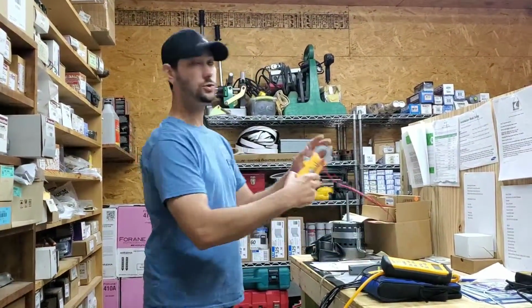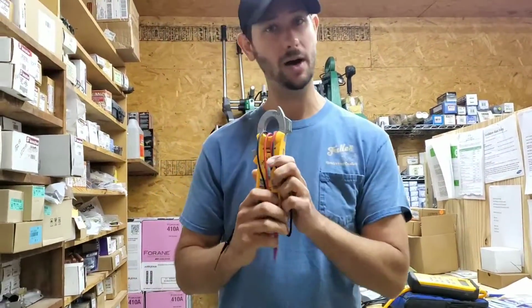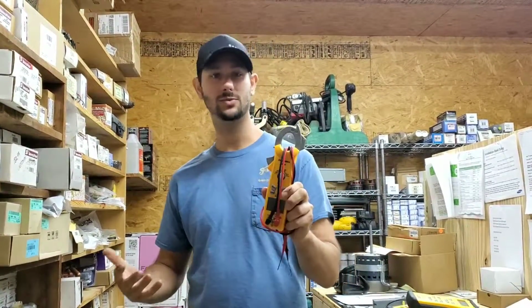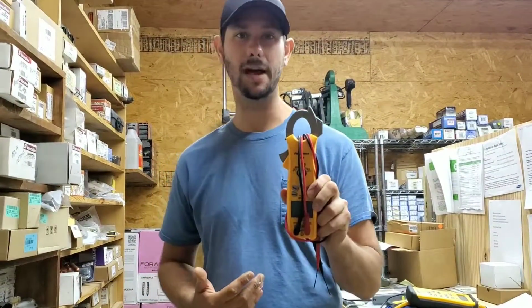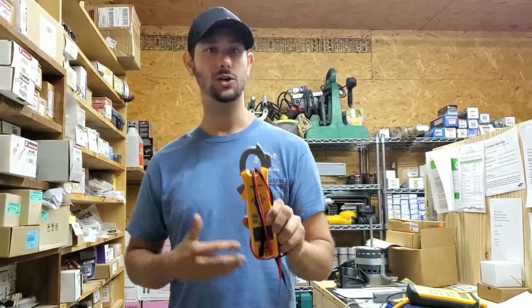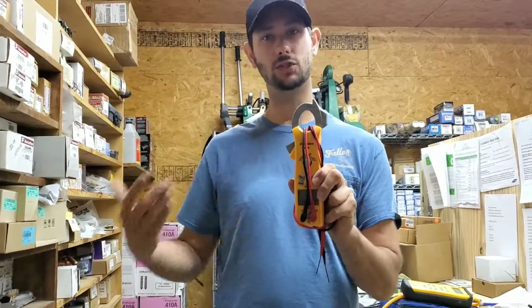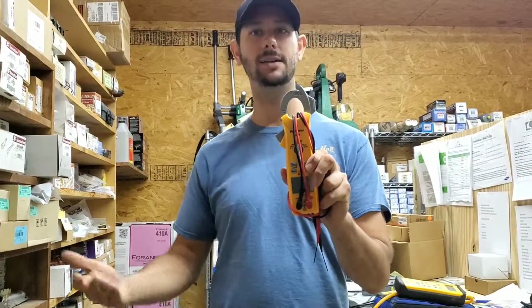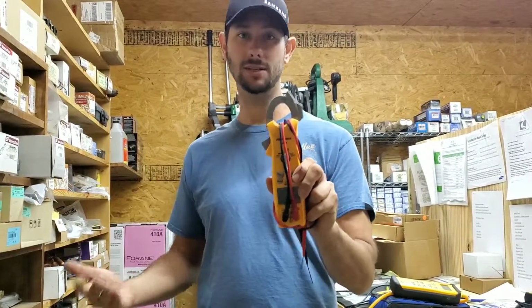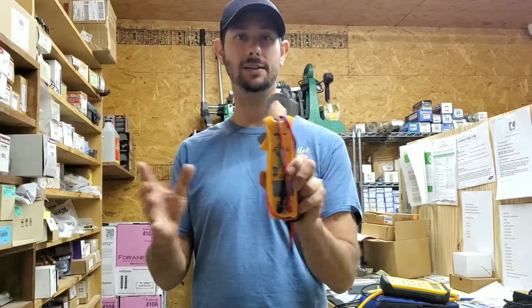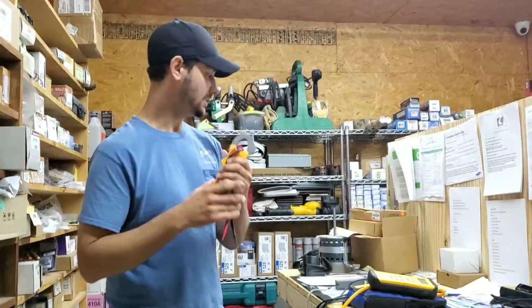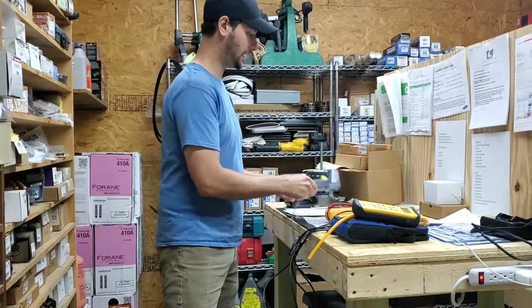So let's go straight to a meter. You definitely need a meter. Why do you need a meter? Because if you're measuring microfarads on a capacitor, trying to see if the capacitor is good, or you're trying to measure a motor and see if it's shorted to ground, has open windings, or to measure the winding resistance and then be able to calculate that, you need a meter, okay? Definitely have a meter. Also measuring amp draw.